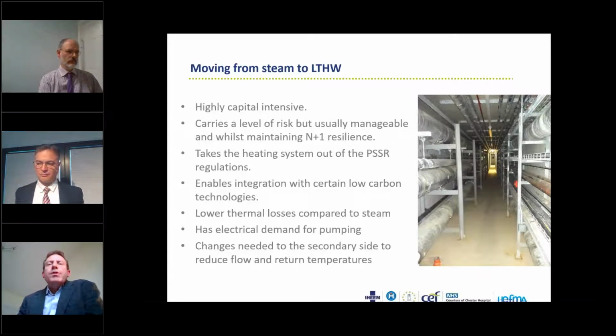So it's a great opportunity to move from steam to low temperature hot water. It's going to be capital intensive and carries a level of risk because we're doing open heart surgery on the hospital, but it should be manageable whilst maintaining N+1 resilience. It will take the site out of the pressure systems regulations, so we avoid costly strip downs and insurance inspections. It's also an opportunity to redesign the distribution system to be compatible with low carbon technology, some we can put in now and some coming in the future. The LTHW will have lower thermal losses compared to steam, and more electrical demand for pumping, but compared to the losses that's small beans.